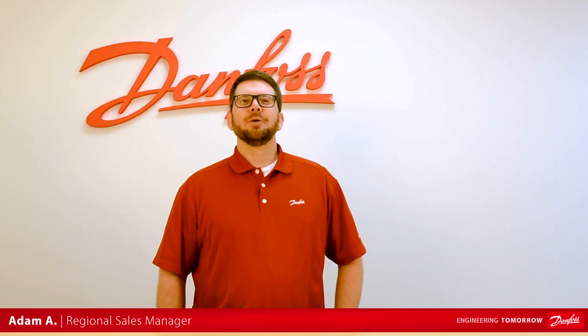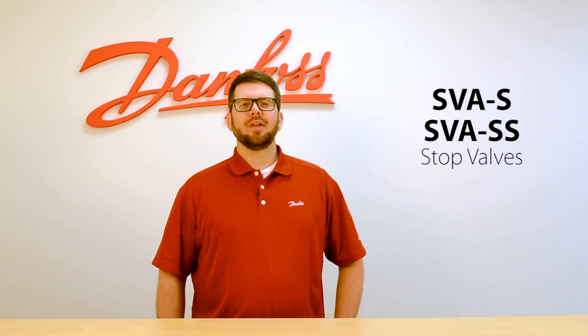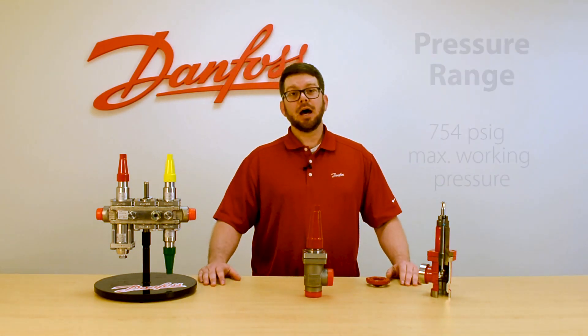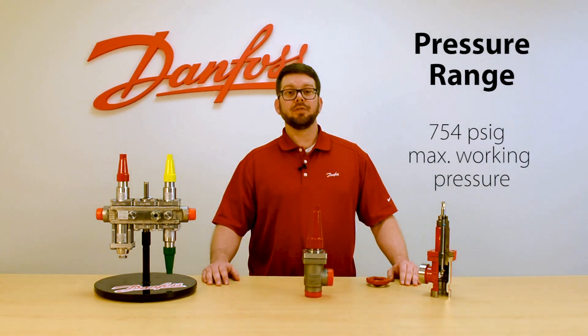Hey, this is Adam with Danfoss and today we're going to be giving an overview of the SVA-S and the SVA-SS stop valves from Danfoss Industrial Refrigeration. The SVA-S is our stop valve from Danfoss. It's part of the SVL family and it shares the same high max working pressure of 754 PSIG and the same large temperature working range of negative 76 to 302 degrees Fahrenheit.